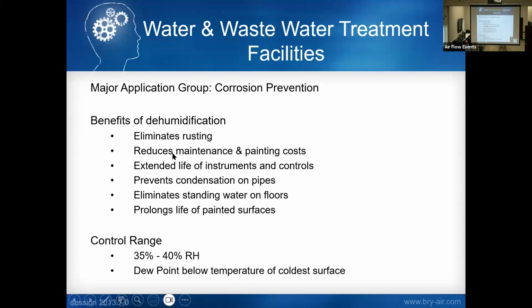Water treatment facilities, typically we see these at about 35 to 40% RH. They try to maintain a dew point below the temperature of the coldest surface, so we use what we call condensate control. We send with the unit a pipe sensor that is mounted on the coldest pipe in that water treatment plant. We get that pipe temperature, send it back to our control unit along with the dew point and temperature of the space, and then we control the unit based on that pipe surface temperature.